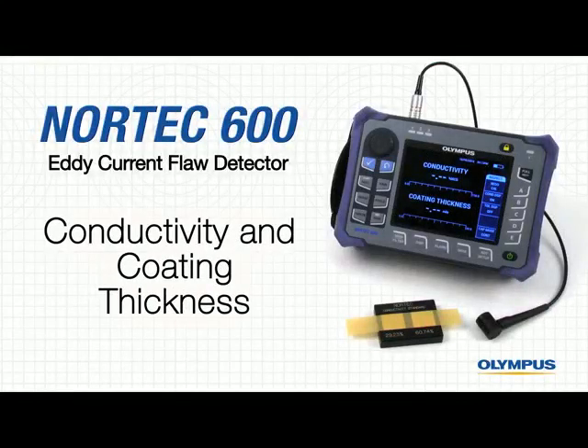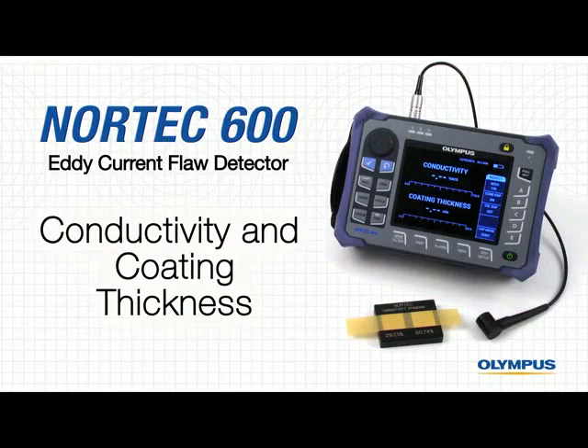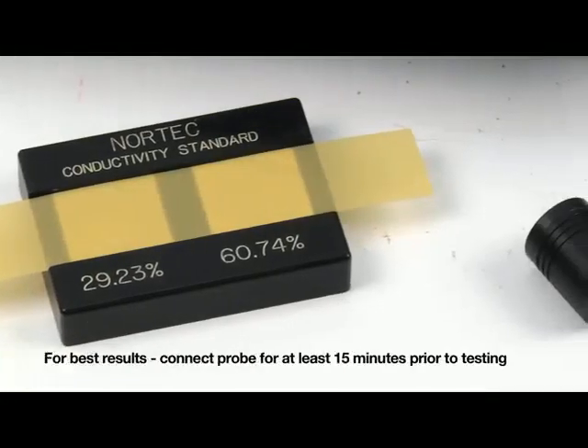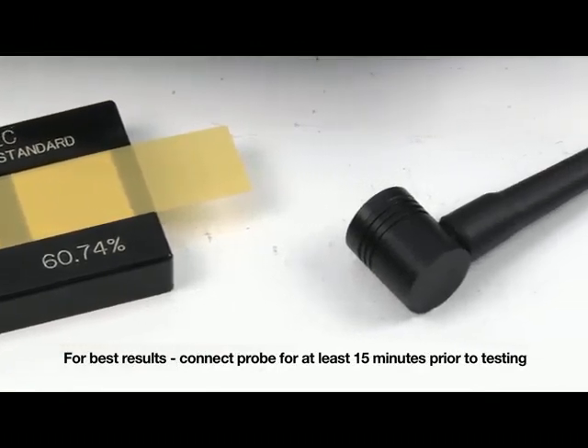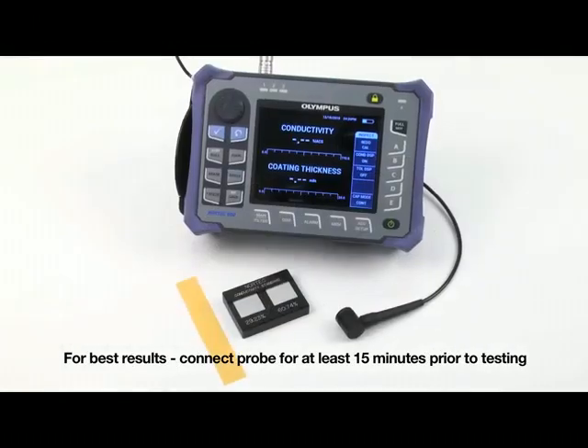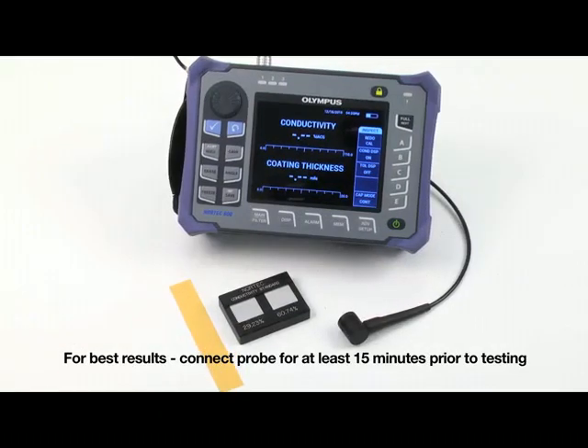The following method is the fastest way to calibrate the Nortec 600 for conductivity and coating inspections. Note that this test is best done with a probe that has been connected for at least 15 minutes to the instrument. This yields more accurate results.